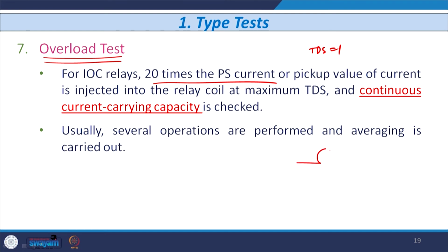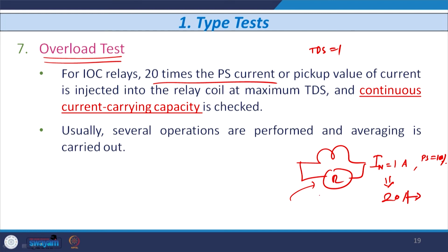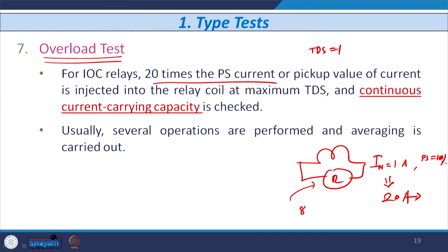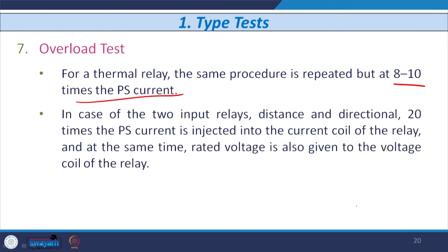Whenever you connect the relay on the CT secondary, let us say the nominal current is I nominal, that is 1 ampere, and the plug setting is 100%. You need to inject 20 times the plug setting current, that is 20 amps, on the CT secondary, and then check the continuous current carrying capacity of the relay coil as well as the contact. Usually several operations are performed and then finally averaging is carried out. If I consider a thermal relay, the same procedure is repeated, but at 8 to 10 times the plug setting. So, in the previous case the current is 8 ampere to 10 ampere for a thermal relay.